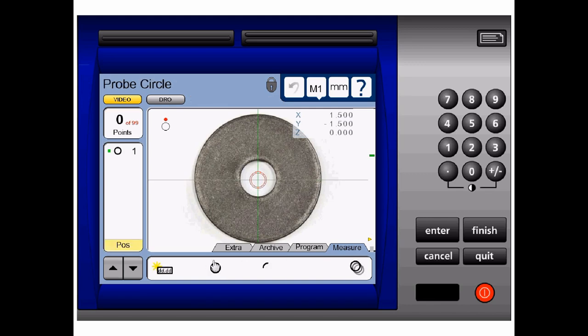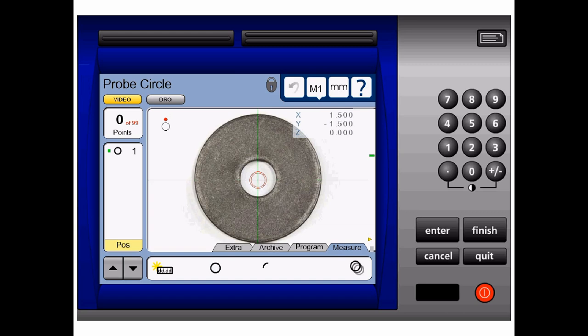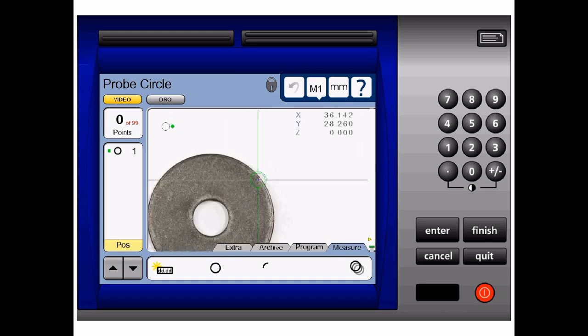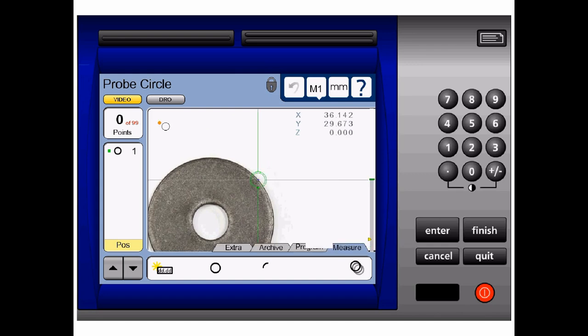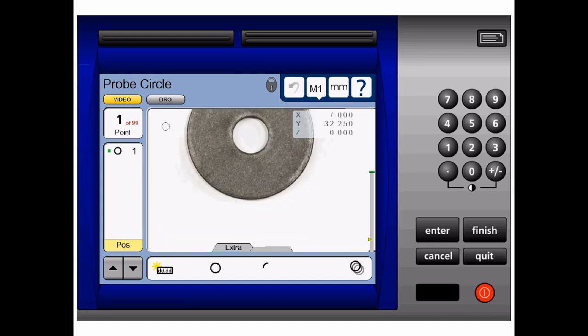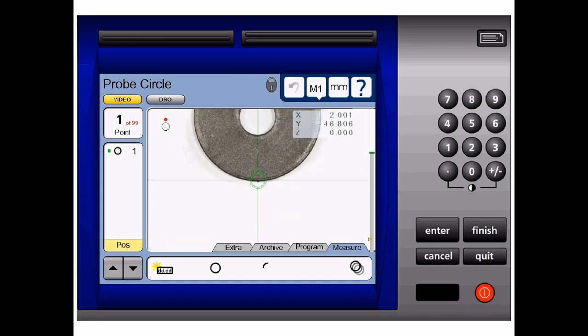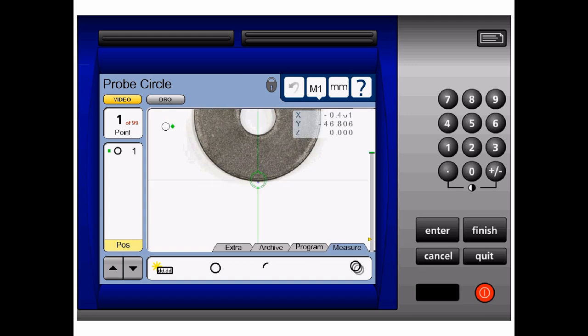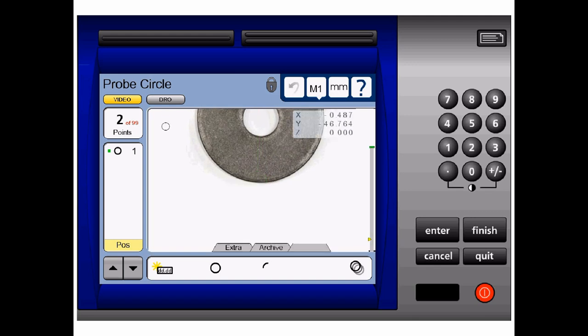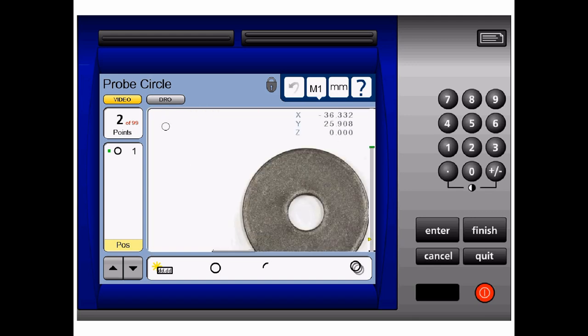Because our outside diameter takes up more than 75% of our field of view, I have to first measure three points around the outside diameter by moving the stage. I shall take one point here, one point at the bottom, and one point here.